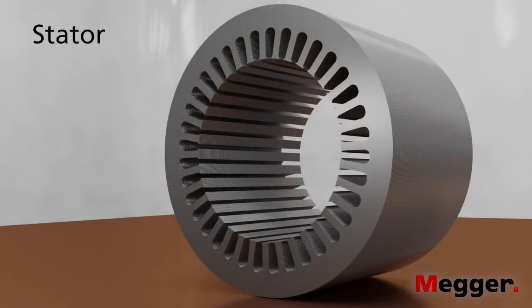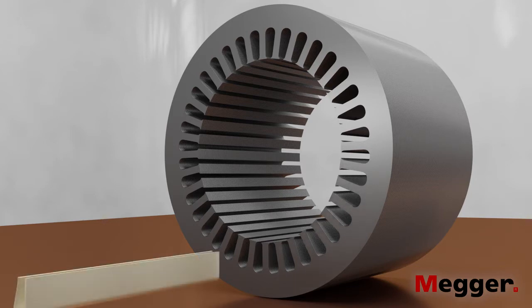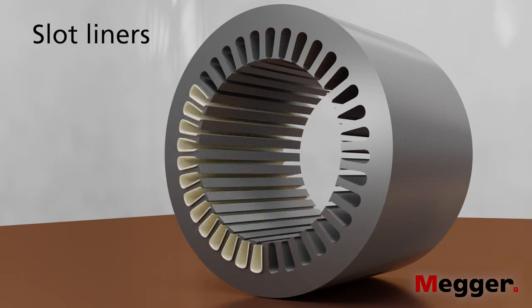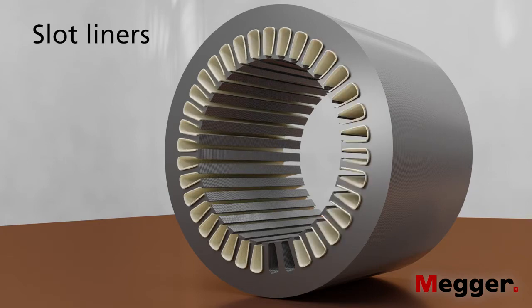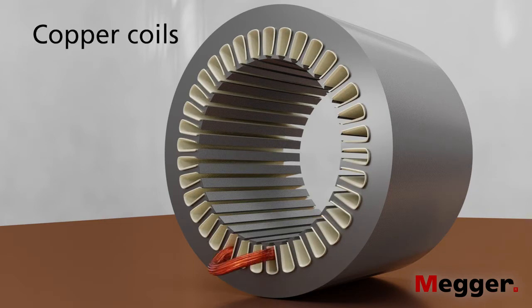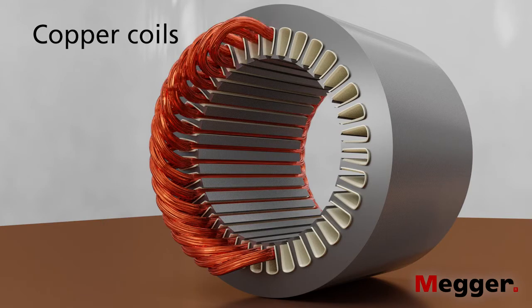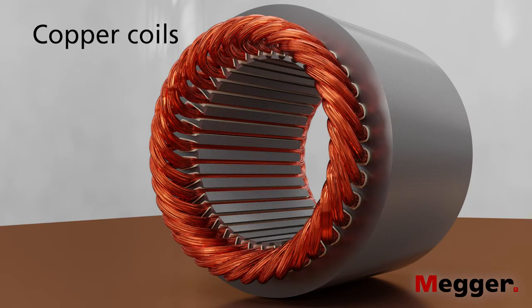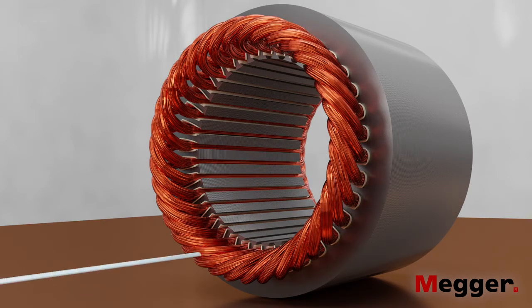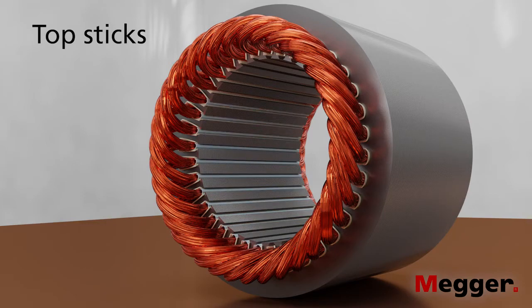If you imagine a stator, it consists of a laminated iron core. The main component of ground wall insulation consists of slot liners, which are inserted before the windings are installed. The windings consist of copper wire, which is coated with an insulating layer. This comprises the turn-to-turn insulation. Finally, additional insulators known as top sticks complete the ground wall insulation.